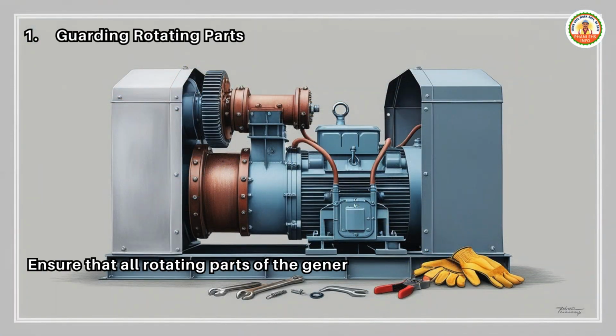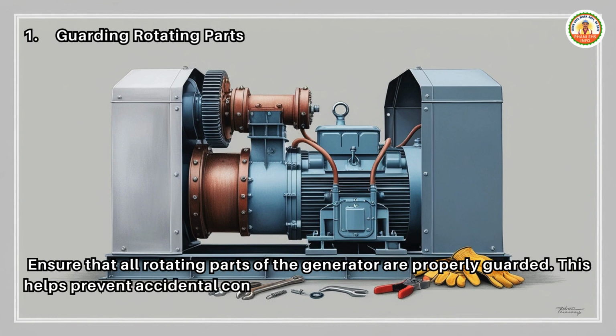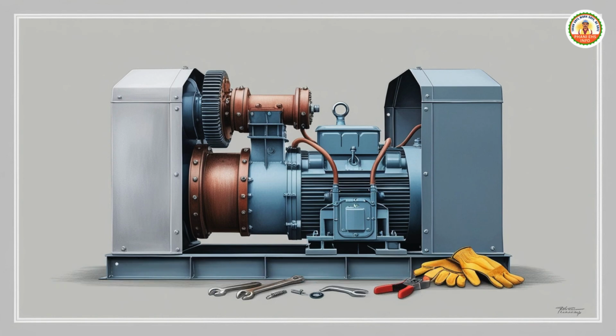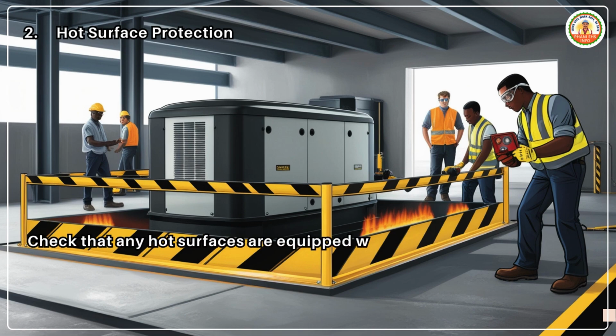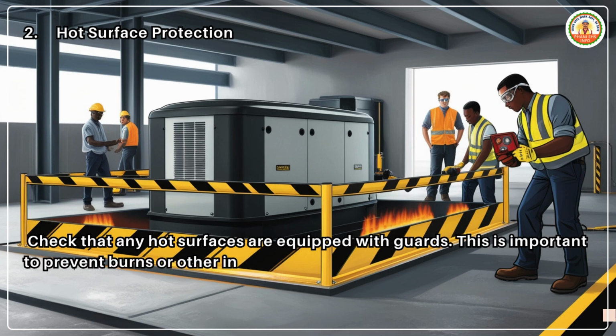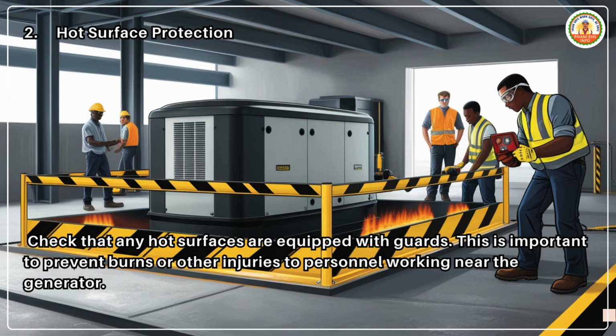1. Guarding rotating parts. Ensure that all rotating parts of the generator are properly guarded. This helps prevent accidental contact and reduces the risk of injury. 2. Hot surface protection. Check that any hot surfaces are equipped with guards. This is important to prevent burns or other injuries to personnel working near the generator.